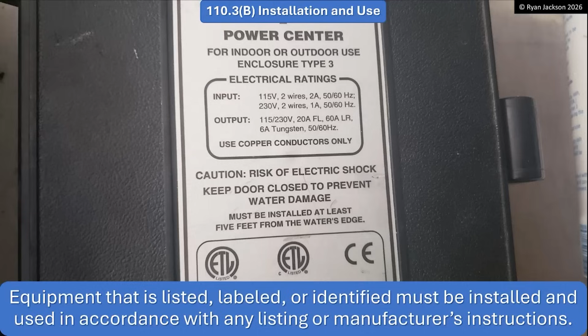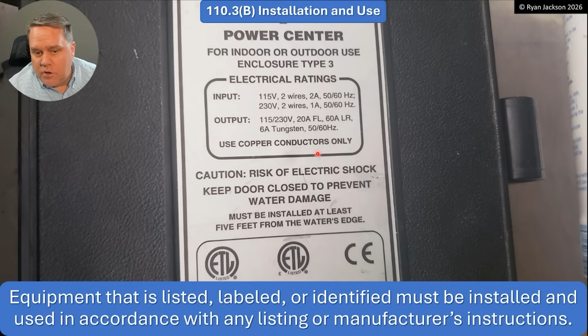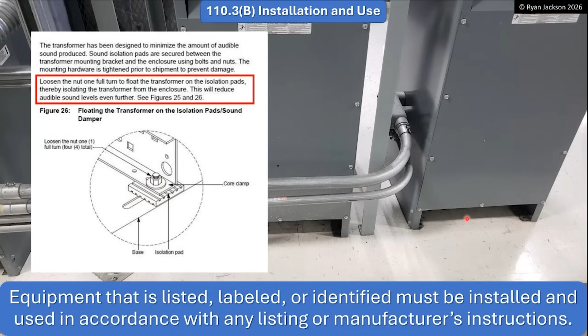110.3(b), like I mentioned earlier, is the rule that says follow instructions. Equipment that's listed, labeled, or identified must be installed and used in accordance with any listing or manufacturer's instructions. So here we have this piece of electrical equipment that says it must be installed at least 5 feet from the water's edge. I'm guessing this is some sort of swimming pool transformer - input and output look different. Copper conductors only, keep it 5 feet from the water. Follow instructions - beautiful thing.